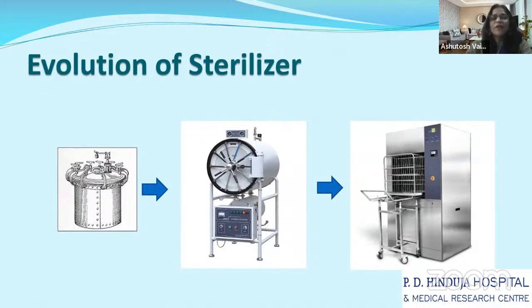We have seen the evolution of sterilizers, right from the basic modes in ancient times, when we probably sterilized by boiling. Then we moved to the pressure cooker, then to manually operated machines, and now we have high-tech machines which are PLC controlled. When we used a cooker or a manually operated machine, the smaller machine does not have a jacket which can control the temperature, one of the most important criteria in sterilization. So the effect of sterilization is lesser than with a high-tech machine. In a manually operated machine, it is manually controlled, so anybody can change the parameters of sterilization, and we are again not confident about the end result.